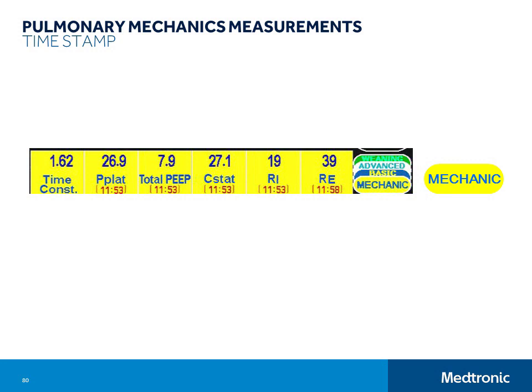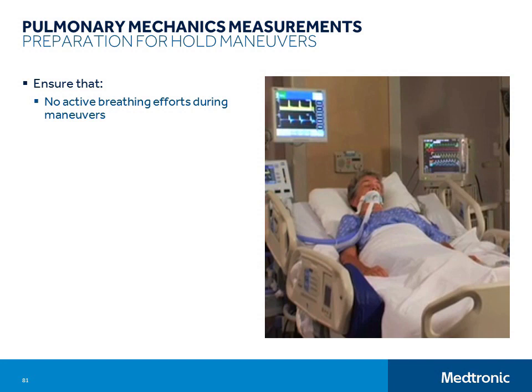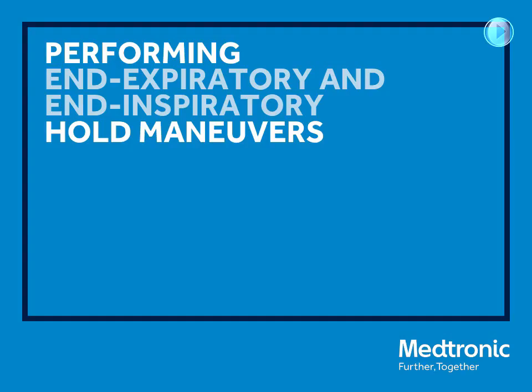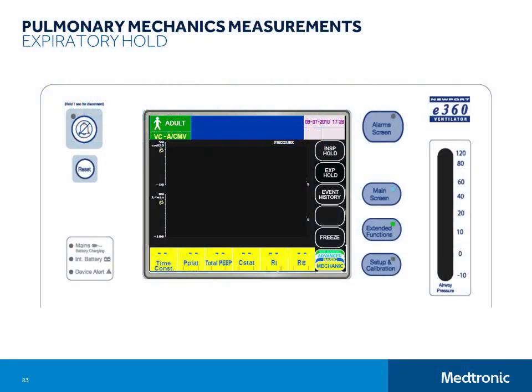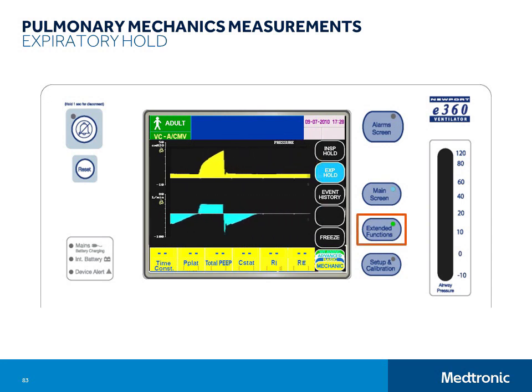Touch the Extended Functions button. Then touch and hold the expiratory hold button and continue holding until past when the next breath is due to begin. Then let go. During the hold, gas flow to the patient is postponed while the exhalation valve is held closed. The airway opening and alveolar pressures equilibrate as the end expiratory state is prolonged. If patient exhalation is passive and the expiratory phase is held until a quasi-steady pressure is achieved, the circuit pressure measurement will provide a reasonable estimate of the average alveolar pressure.